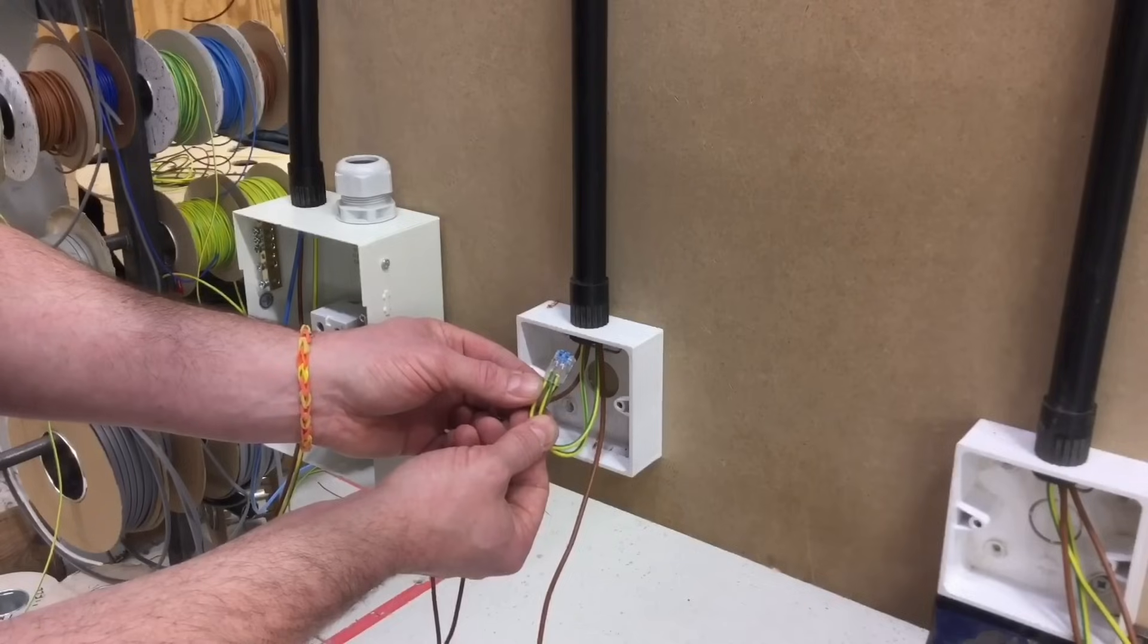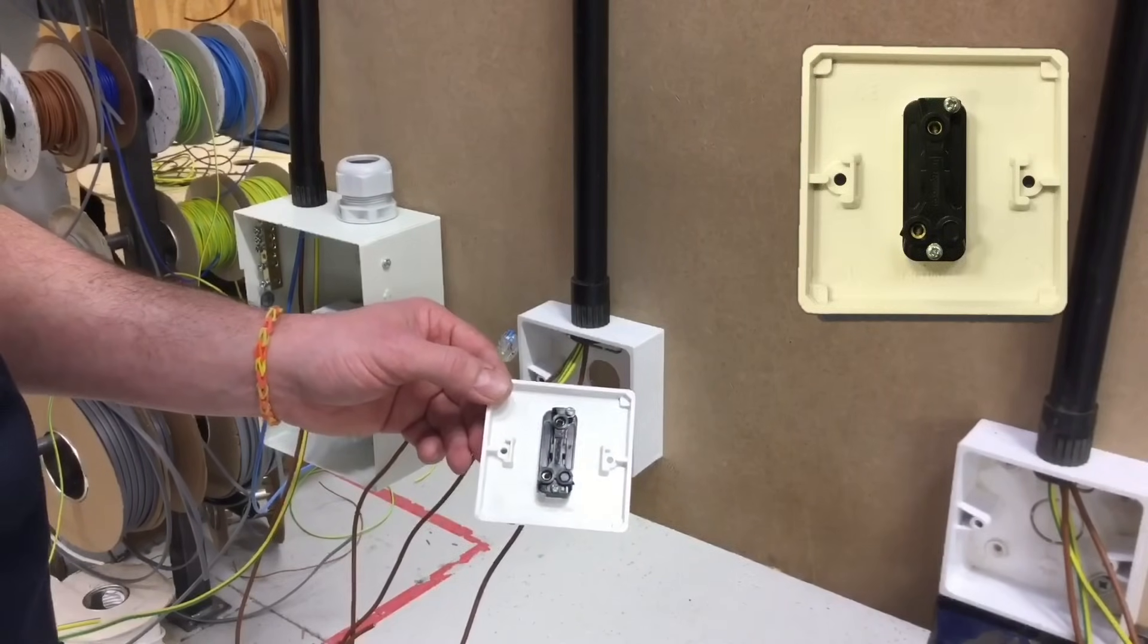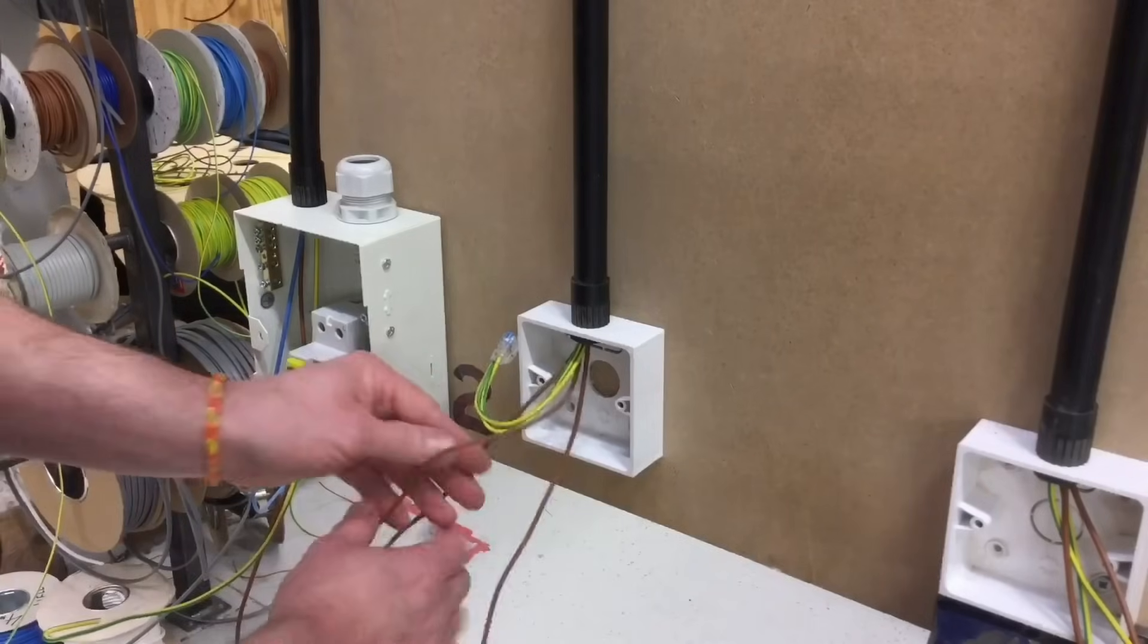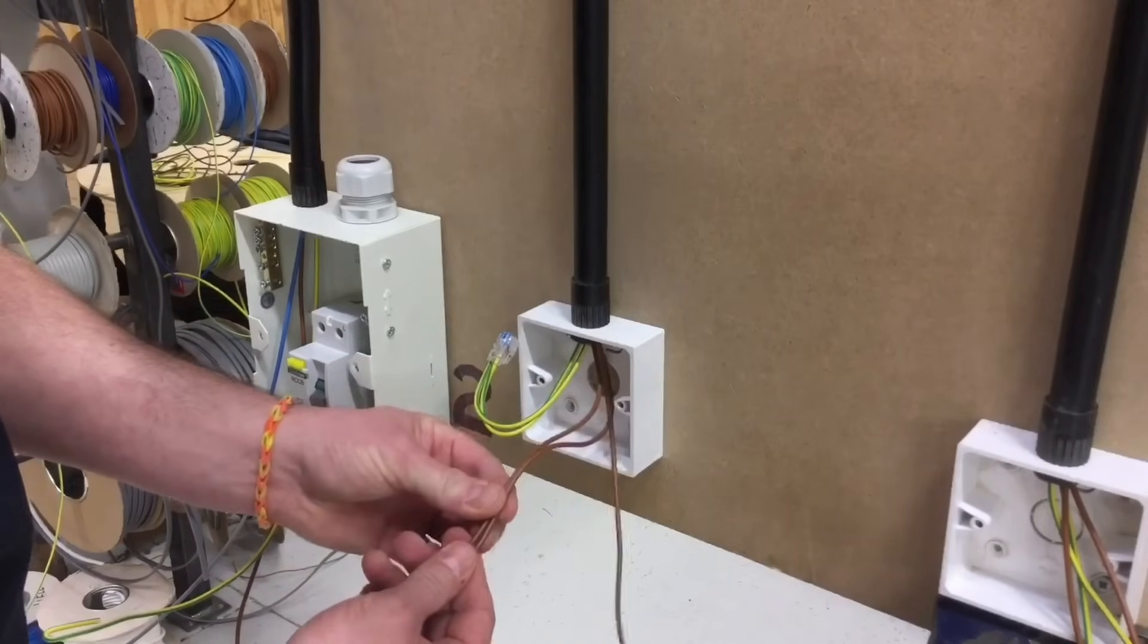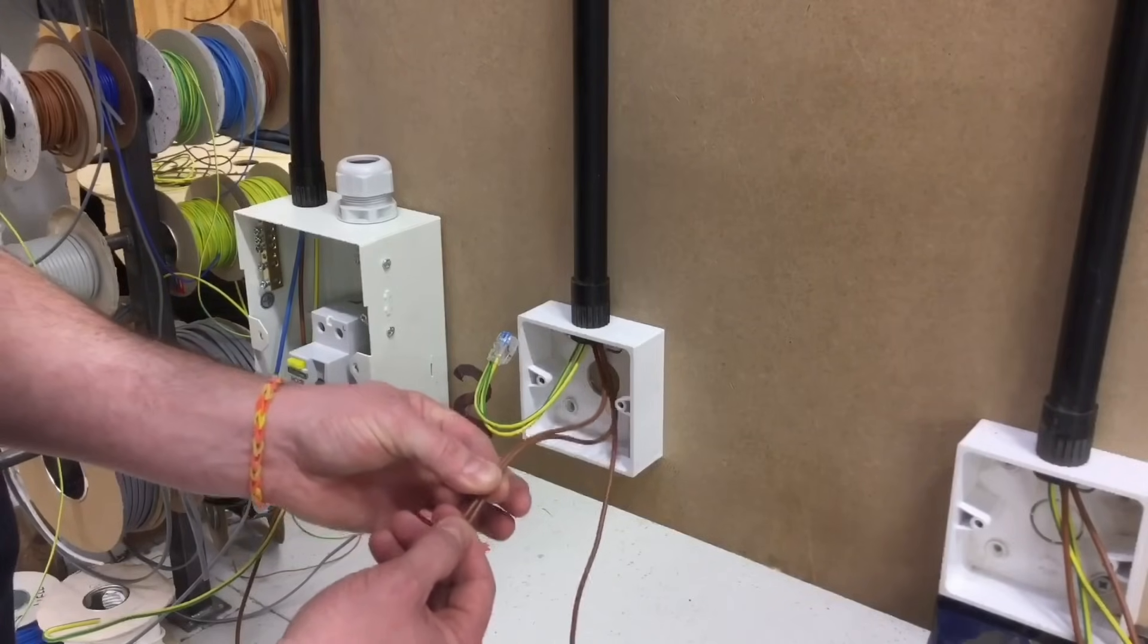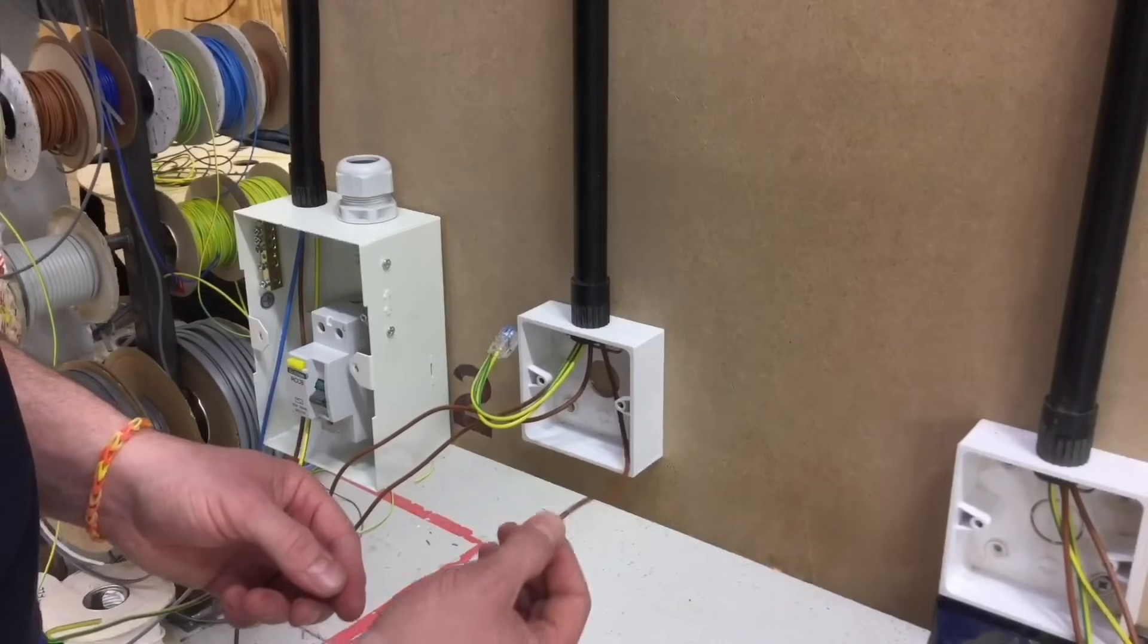Our two CPCs are in a maintenance-free connector held in the back of the box, not needed to be connected to the box itself because it's plastic, not needed to be connected to the switch because it's plastic. Neither of them are an exposed conductive part, but they are there in case the customer changes it to a metal fronted light switch. Let's move on to the line and switching line conductors next.